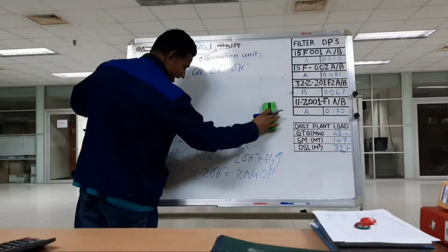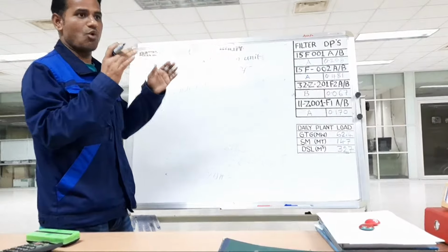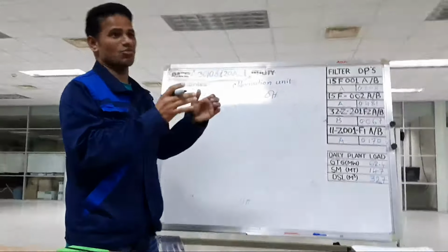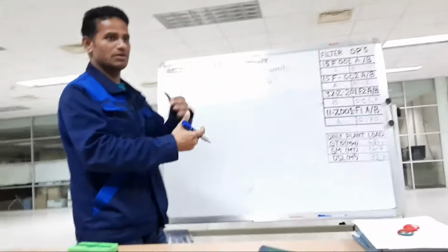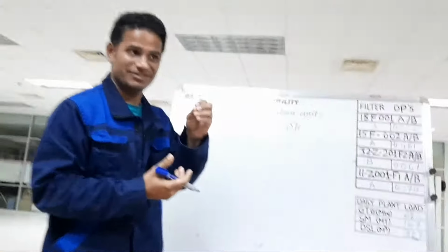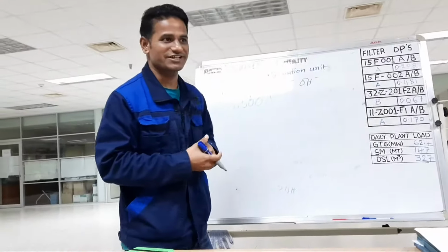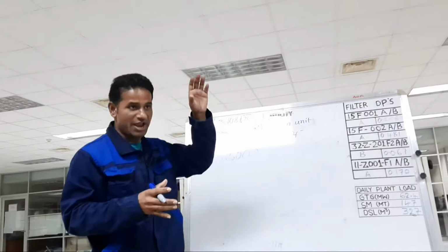Clear or not? But in 100% production, the hypochlorite generator current is 8500 ampere maximum. So now we found 197 meter cube of sodium chloride, sodium hypochlorite and water. This product will enter the hypodosing storage tank with hydrogen. All this product will enter the hypodosing storage tank. Clear?